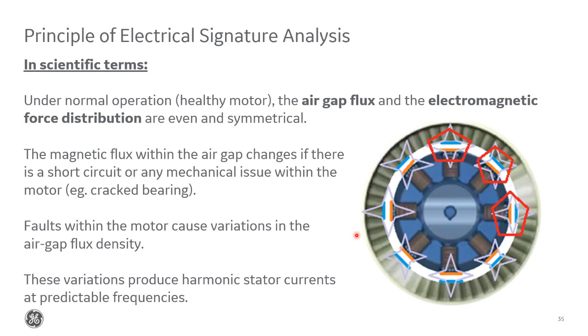And so here we're basically saying the same thing, but in more scientific terms. Under normal conditions, the air gap and the flux all the way around the periphery of the rotor and stator should be even and symmetrical. Any physical anomalies will affect the magnetic flux in some way, which will reflect back onto the stator current as noise at specific predictable frequencies.